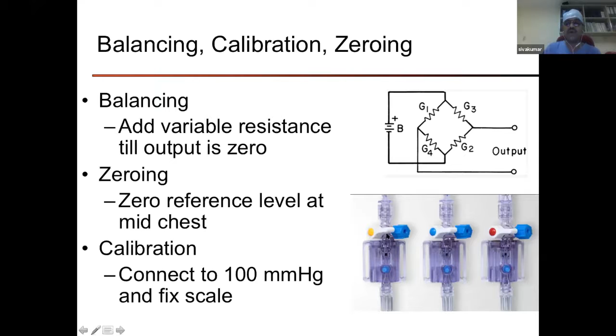We have to find out whether 100 millimeters of mercury is equivalent. In the olden methods, a mercury manometer is connected and inflated to 100 millimeters, and you see whether the pressure trace goes to 100. But today's machines are auto calibrated. So if you press the auto calibration button, it immediately gets calibrated.